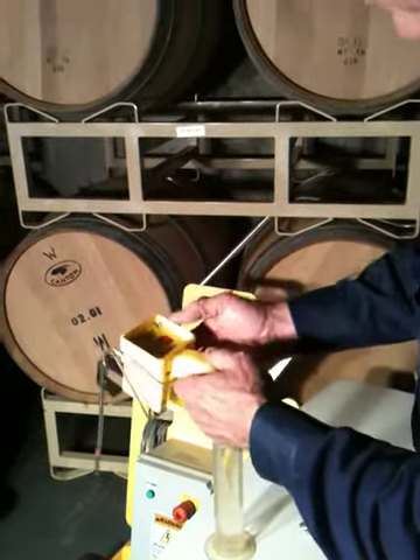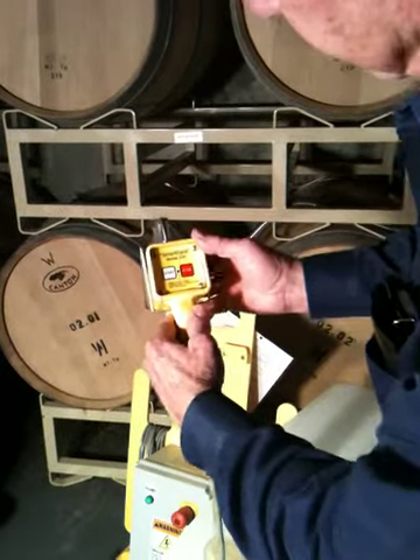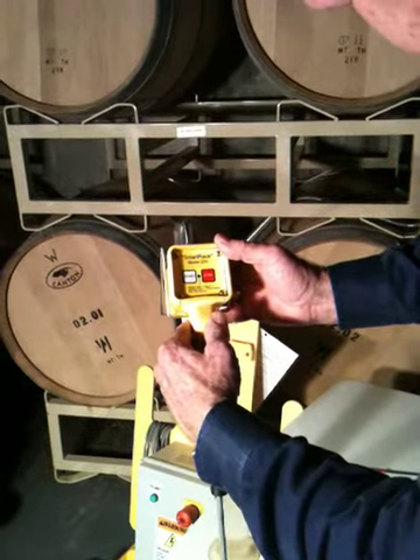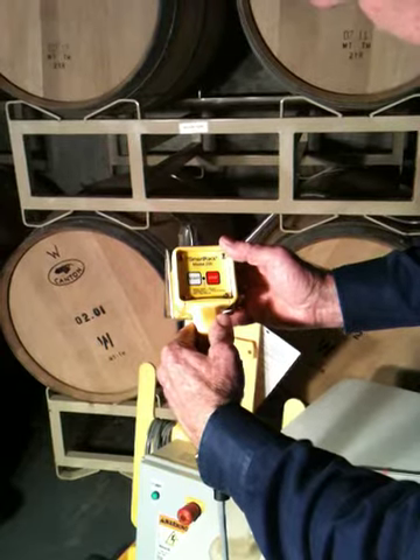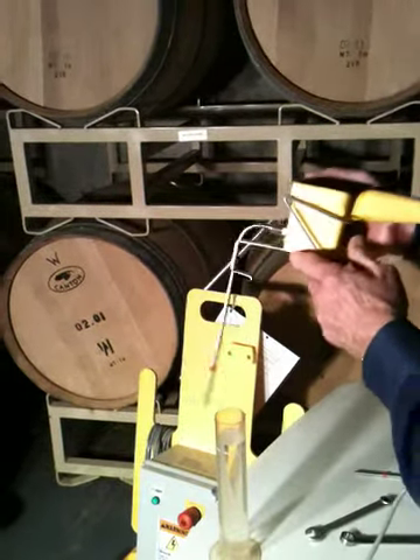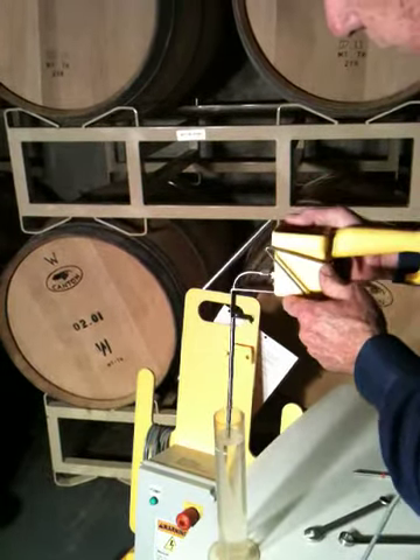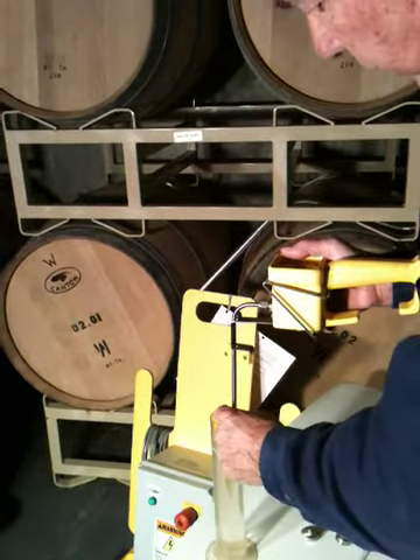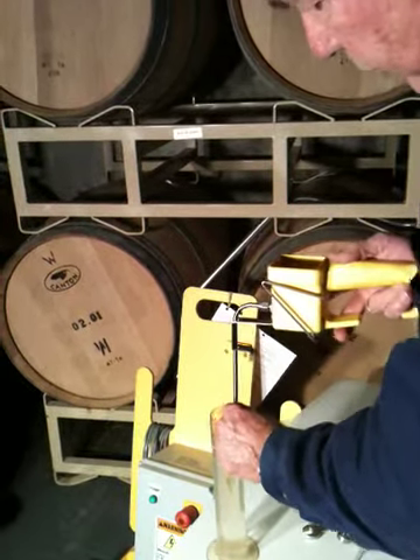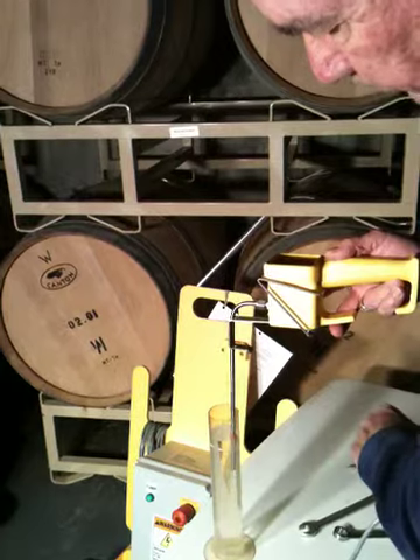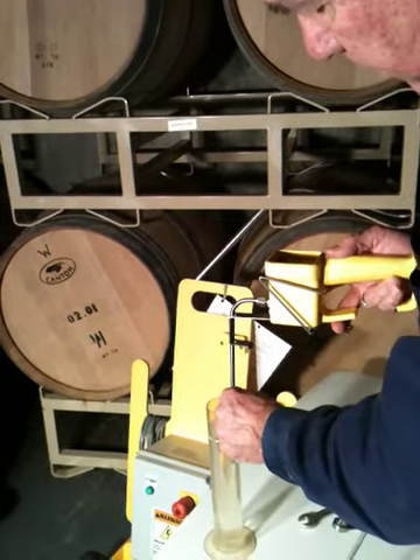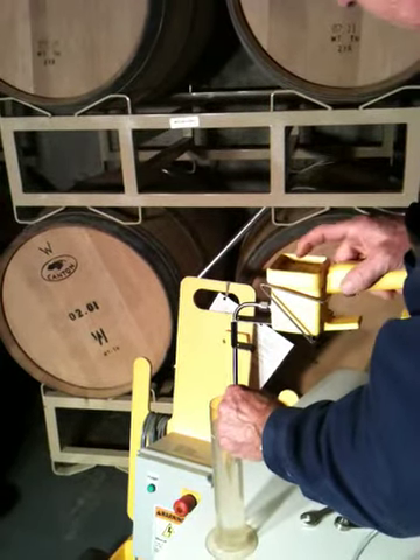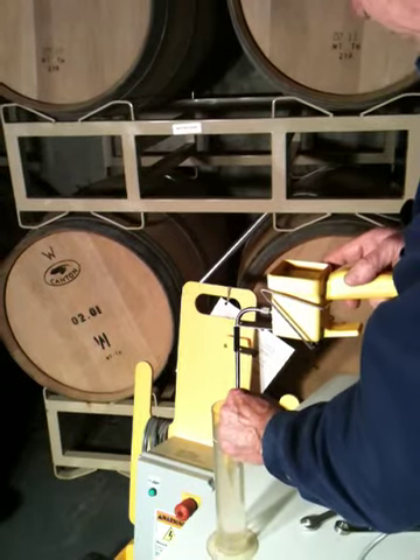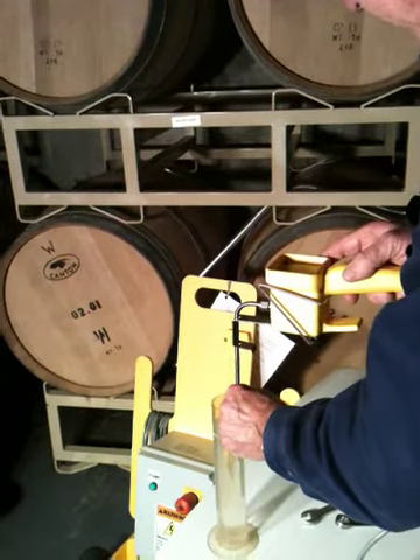And now we hit the start button. And that's going to take us into the leak test. And there it is. It flashed red and went off. So now we're in the leak test mode. Now, we want to give it some pressure so that we can see if it's leaking. So make sure you have a minimum of 2-inch insertion in a liquid column of water. Hold it steady, and then you hit the start button. And when you do, you'll notice the LED is flashing between red and green, red and green.